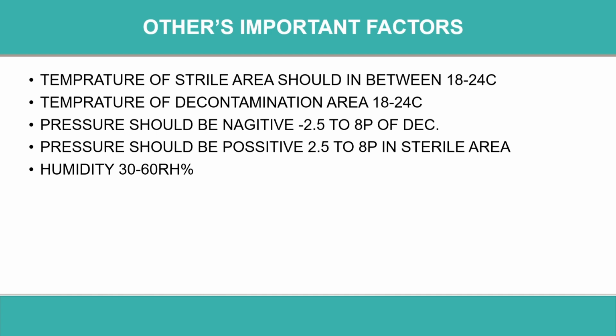In the CSSD department, the temperature should be between 18 and 24 for the sterilization and packaging areas. If we talk about the decontamination area, the temperature should be 18 to 20. For the decontamination area, the pressure should be negative. It is a minimum range, like negative 2.5, at least, but not less than minus 2.5.